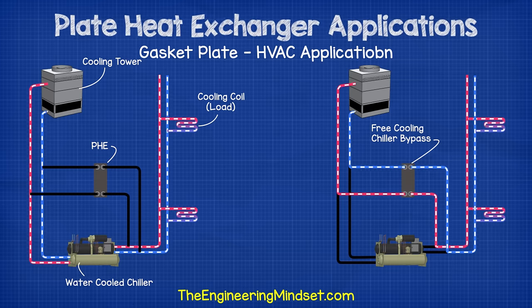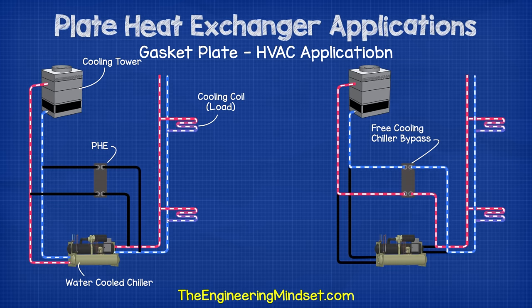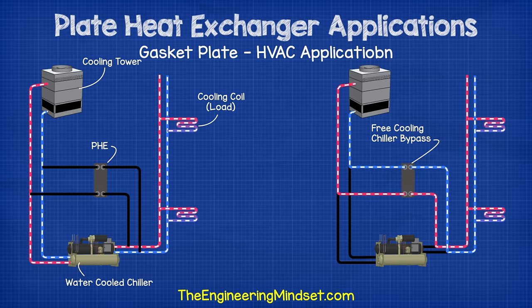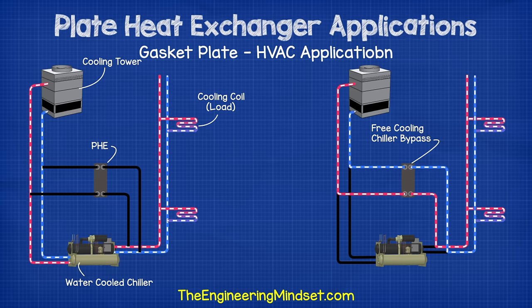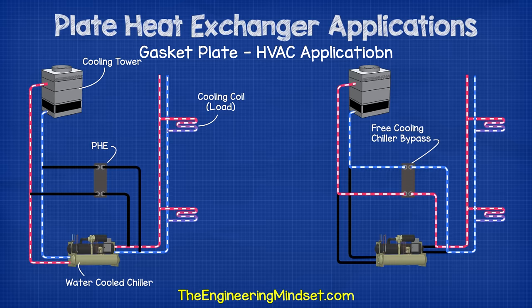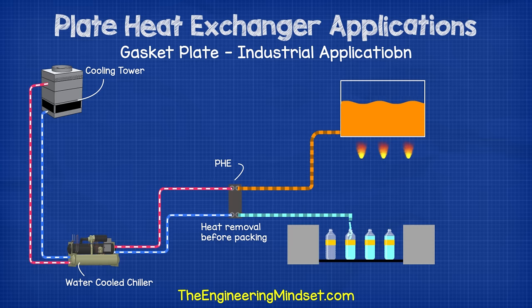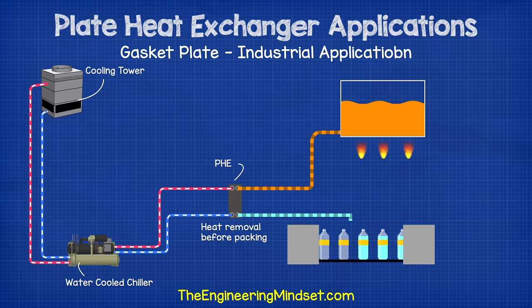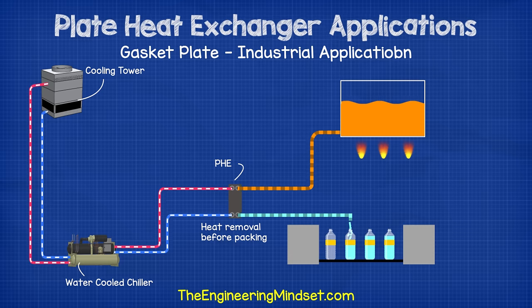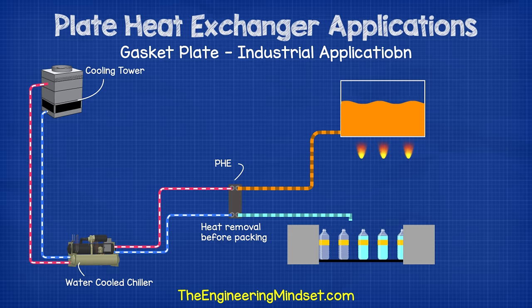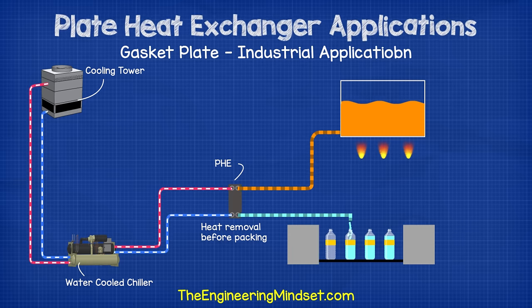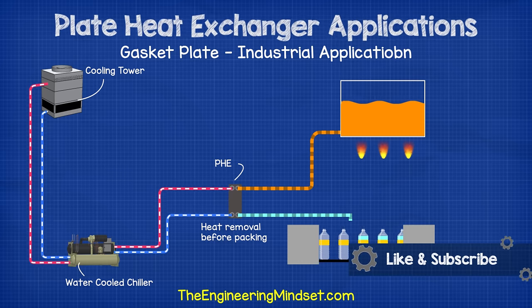In HVAC, you'll find gasket plate heat exchangers used to indirectly connect chillers, boilers, and cooling towers to central plant systems. They're also used for economizer circuits and heat recovery circuits to reduce the cooling load on chillers. In industry and manufacturing, many plants use plate heat exchangers for pasteurization and waste heat recovery. For example, a manufacturing plant may use chilled water to cool a newly manufactured beverage product — the hot liquid passes through a plate heat exchanger connected to a chiller's cooling circuit, extracting heat without the two fluids mixing.